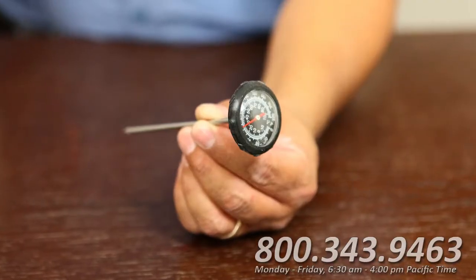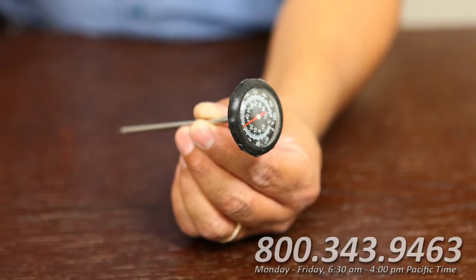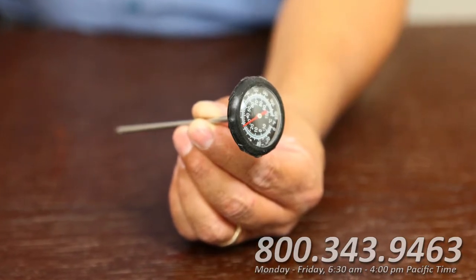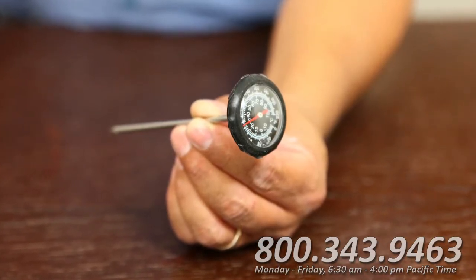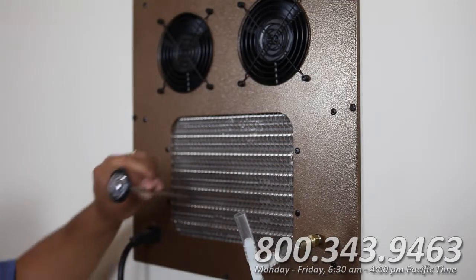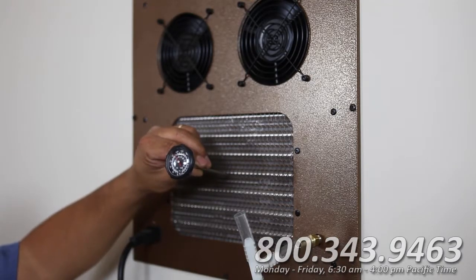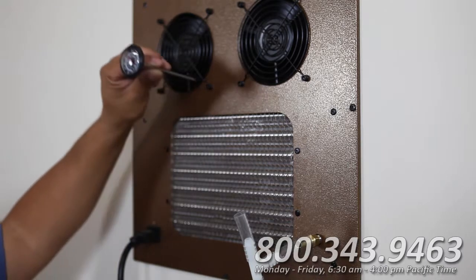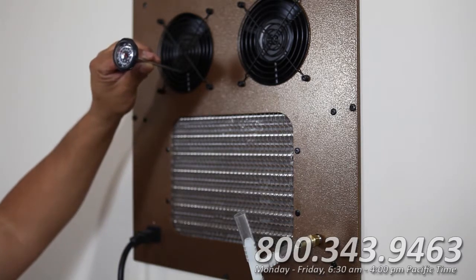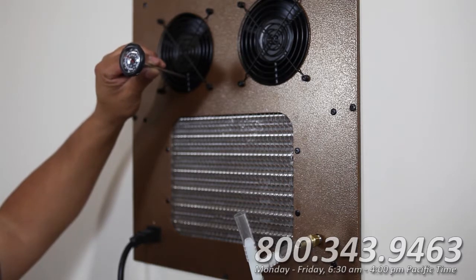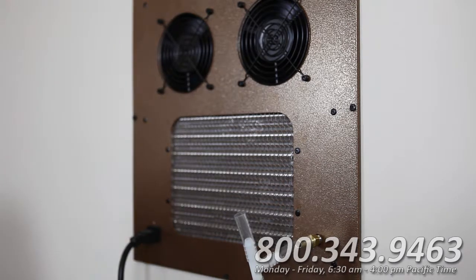If you call customer service, they'll ask you to perform a temperature test. Take a thermometer like this one that you would normally use to test the temperature of cooked meat. Take the temperature of the unit in 3 places: in the center of the condenser coil, in the center of the evaporator coil, and in front of the fans. Don't tape the thermometer to the unit or you can get a bad reading. Just hold it in place until you get an accurate reading.